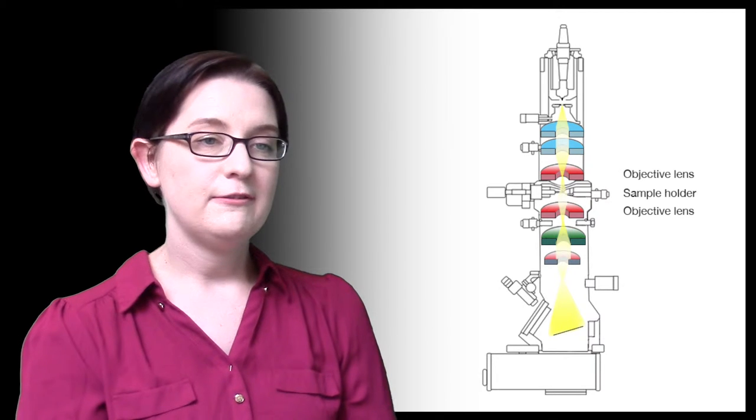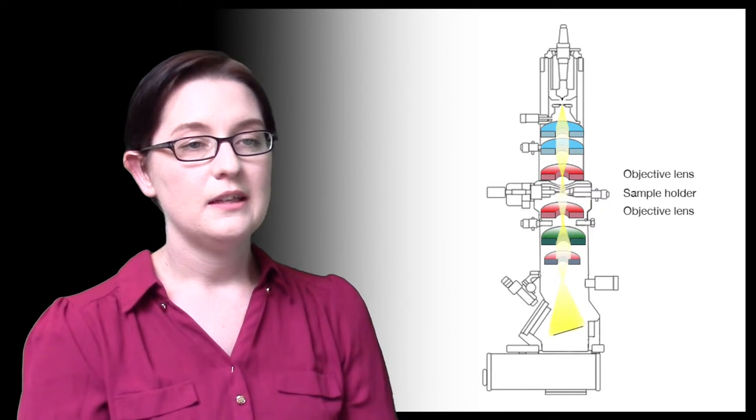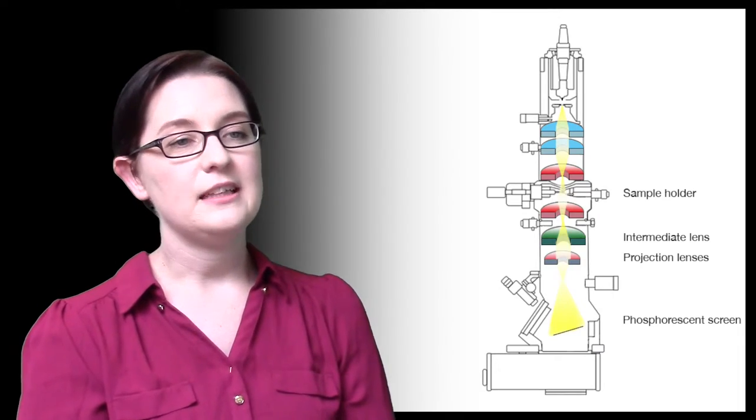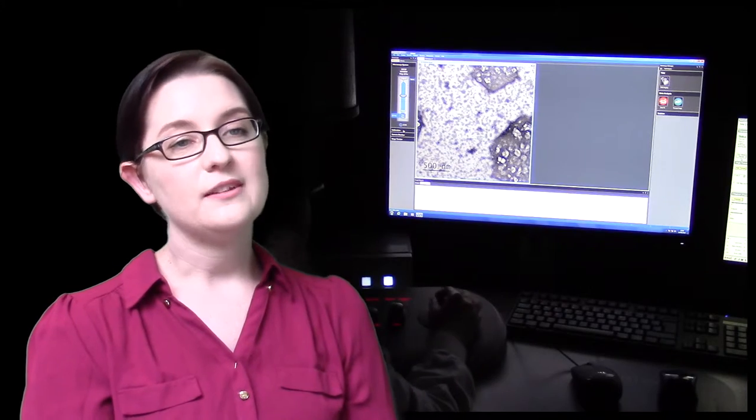Contrast is generated by differential scattering of electrons, and then the intermediate and projection lenses further magnify the image. When the electrons hit the phosphorescent screen in the projection chamber, photons are generated which allow the human eye to view it.